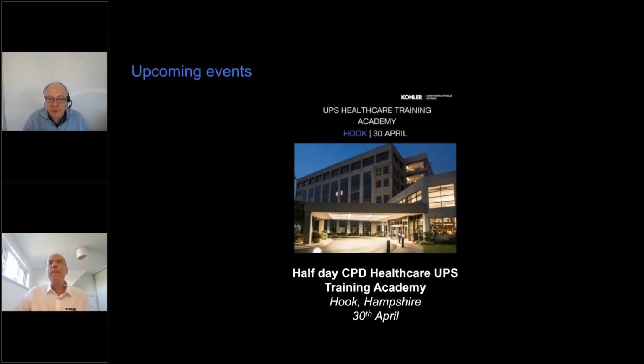Alex, if I may go ahead with one or two of the questions. Sure. One audience member said, I have a question regarding the battery isolation switches typically installed next to batteries. The gentleman says, based on site experience and issues, it seems these switches would be better placed outside the battery room. This would allow the batteries to be isolated during an incident such as a fire or discharge, as smoke and fumes might prevent the batteries from being disconnected. He says, have you had any issues with this, and how would you recommend this being put into the design, etc.? Okay.